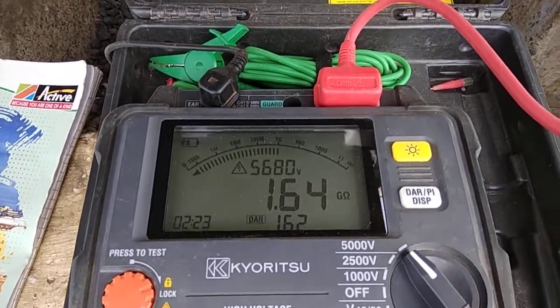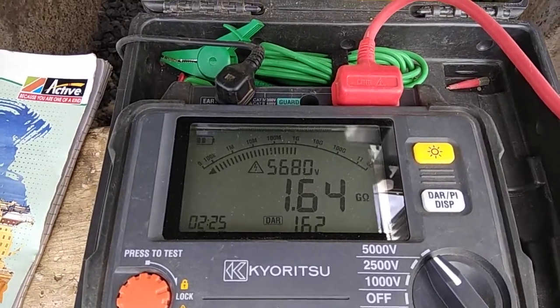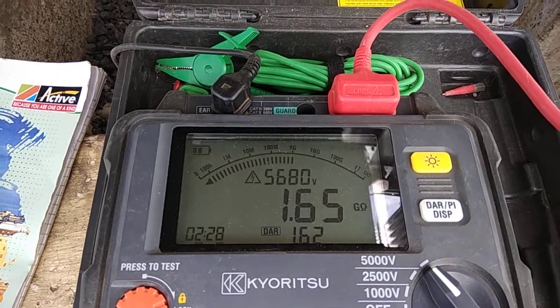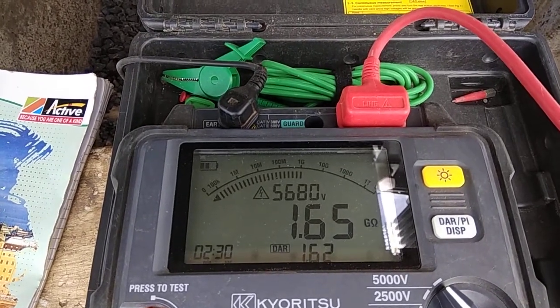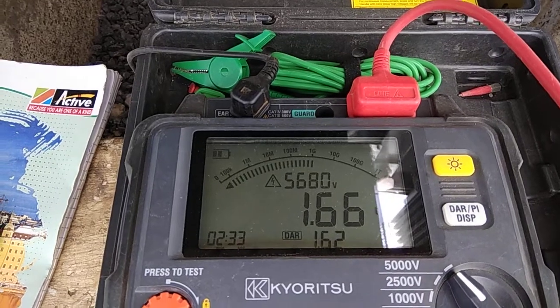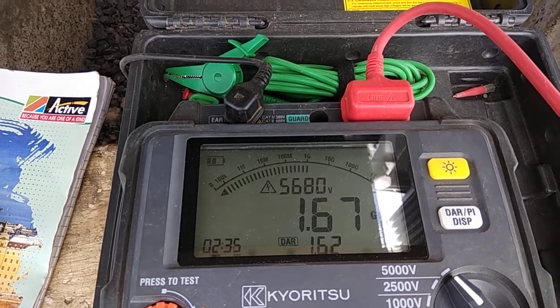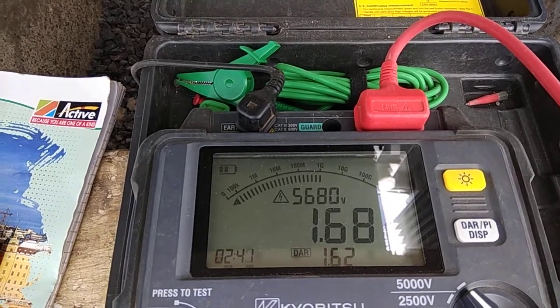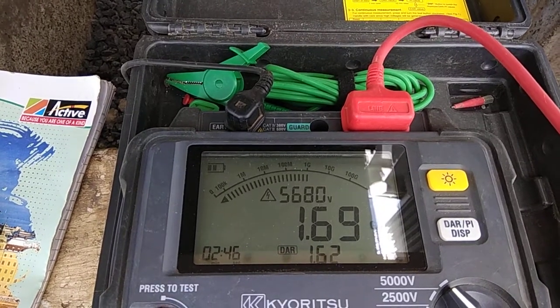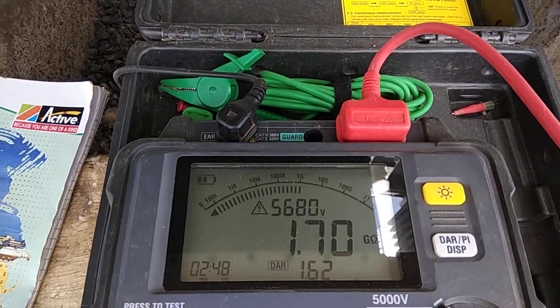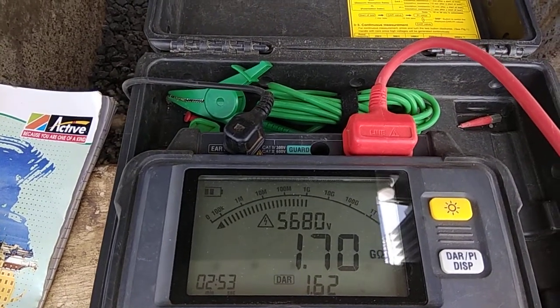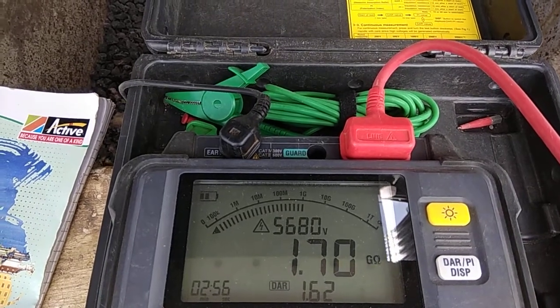Third is the surface leakage current. In the surface leakage current, what happens is every insulator absorbs some kind of moisture and dust particles, so the current starts to leak from the outer surface of the insulator. As time increases, due to the heat, the moisture vaporizes and this current significantly decreases, but we can't say that it is eliminated. So in the insulation test, basically we consider the conductive current, and second, some fraction of the surface leakage current.